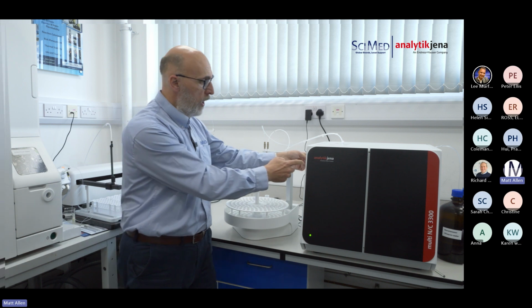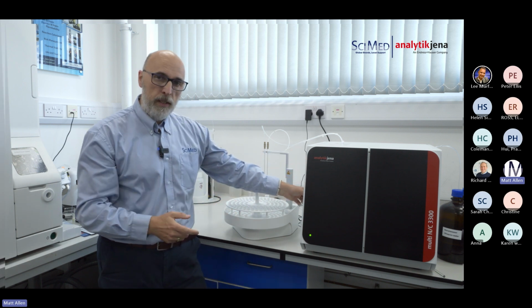The catalyst will typically last you about a year or so. It's one of the things that a lot of times the engineers will change at the preventive maintenance visit. Again, if you're a high throughput lab or particularly dirty samples, then you might change the catalyst a bit more often. It's very simple. Side panel comes off, combustion tube sits in the furnace, take it out, empty it. You can regenerate the catalyst a couple of times or just refill it back up. It's very easy to do.